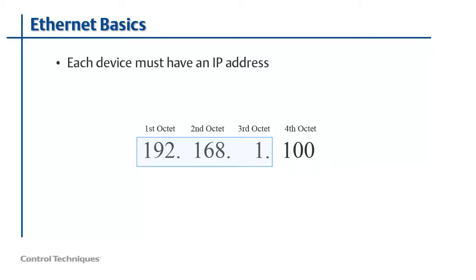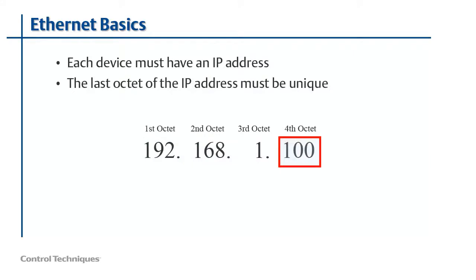Before we look at how to set up the drive, let's take a minute to discuss some Ethernet basics. Every device on an Ethernet network needs what's called an IP address. IP stands for Internet Protocol. An IP address is made up of four 8-bit numbers called octets. It's important to understand that the first three octets of the IP address define the subnetwork. The devices on the network need to have the first three octets of the address be the same, while the last octet must be different for each device.